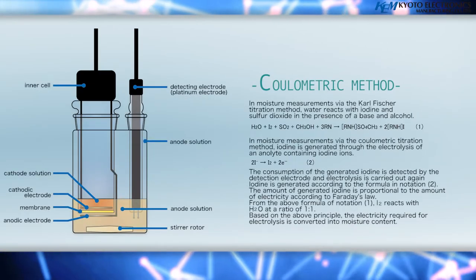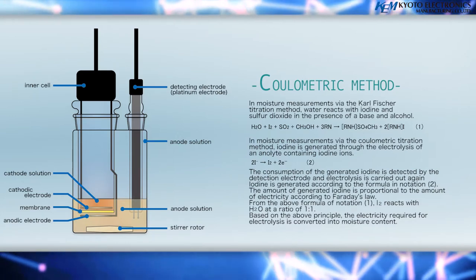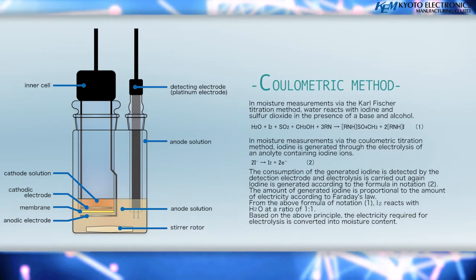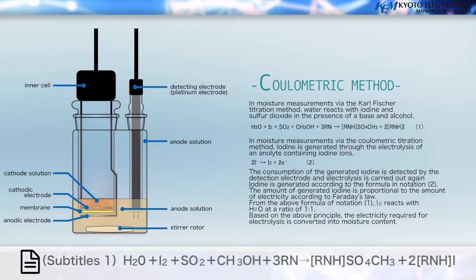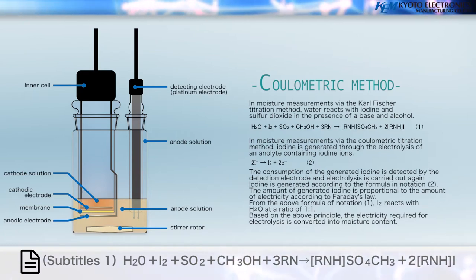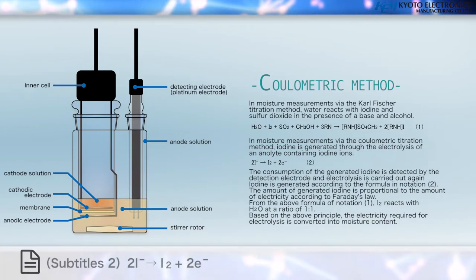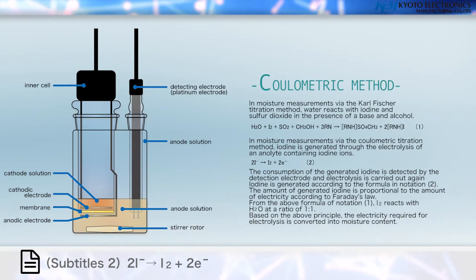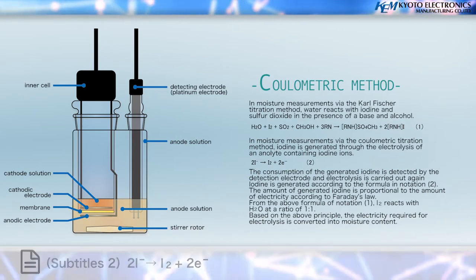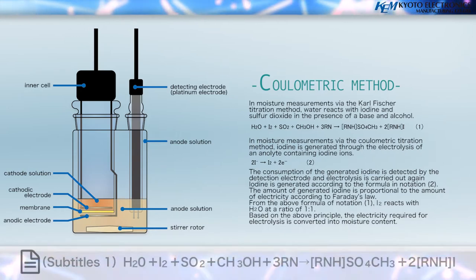In moisture measurements via the Coulometric Titration Method, iodine is generated through the electrolysis of an analyte containing iodine ions. The consumption of the generated iodine is detected by the detection electrode, and electrolysis is carried out again. Iodine is generated according to the formula in Notation 2, and the amount of generated iodine is proportional to the amount of electricity according to Faraday's Law.